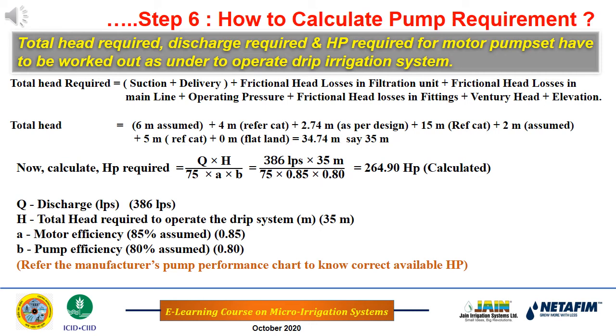Now calculate HP required. HP formula is Q into H divided by 75 divided by A divided by B. Here discharge is 386 liter per second. Total head required is 35 meter. Motor efficiency is 85%. Pump efficiency is 80%. After multiplying all these factors, the HP required comes to 264.90 HP. To know the correct HP of the pump, please check the performance chart of the manufacturer.